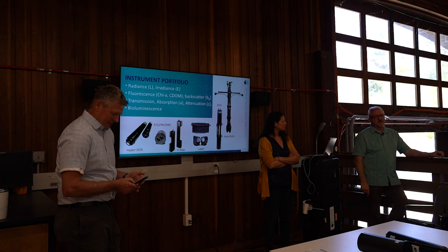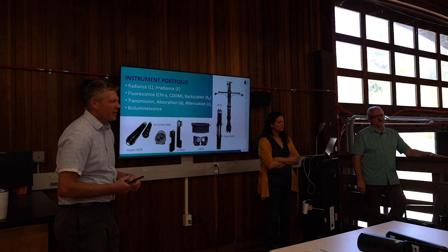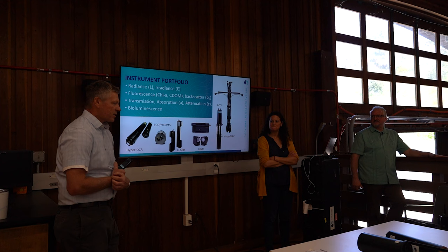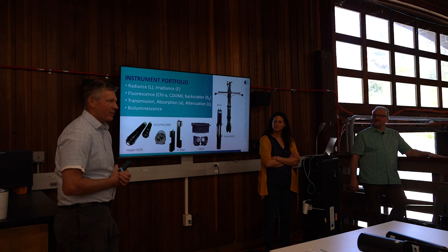As a Navy oceanographer for 31 years, ships that go out in the ocean hardly foul, while ships that sit in the bay need cleaning every three months. The big difference is the turbulence at the very surface. The suggestion was: why not line the tubes with corrugated Teflon and speed up the flow? We definitely actually rely on turbulence in the region to reduce the effects of boundary layers within the tubing. That's important because it affects the response time of temperature and conductivity sensors. The dimensioning and geometry is chosen for that reason.